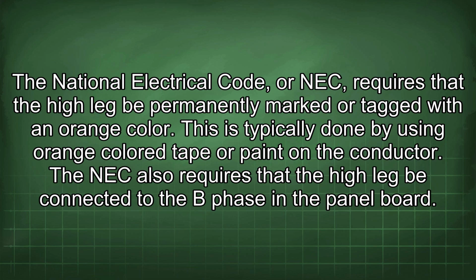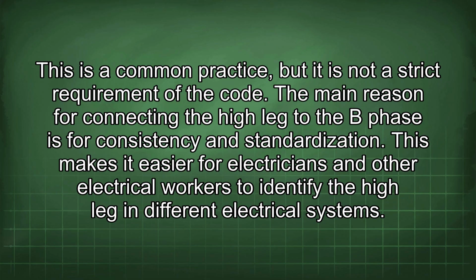The NEC also requires that the high leg be connected to the B phase in the panel board. This is a common practice, but it is not a strict requirement of the code. The main reason for connecting the high leg to the B phase is for consistency and standardization. This makes it easier for electricians and other electrical workers to identify the high leg in different electrical systems.